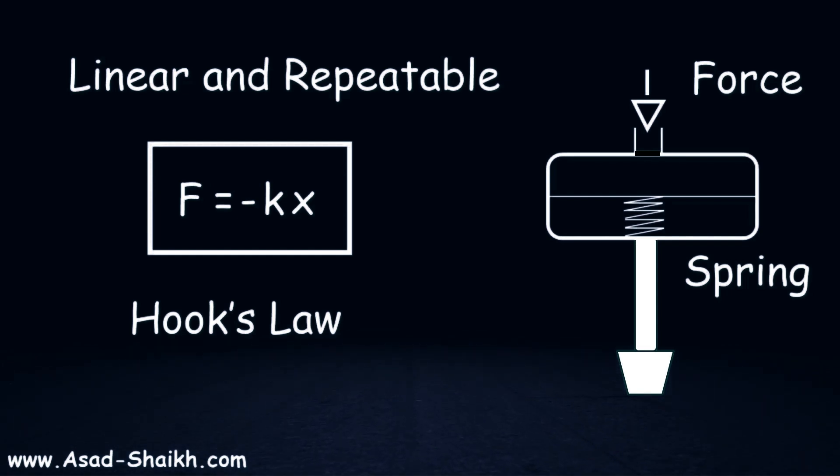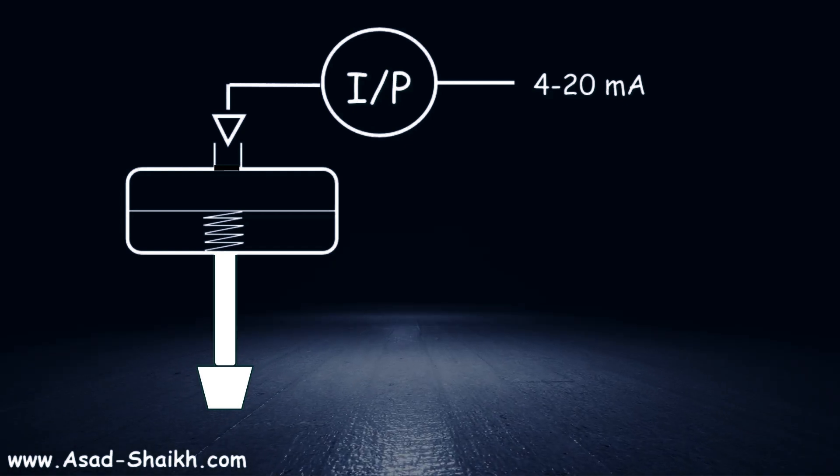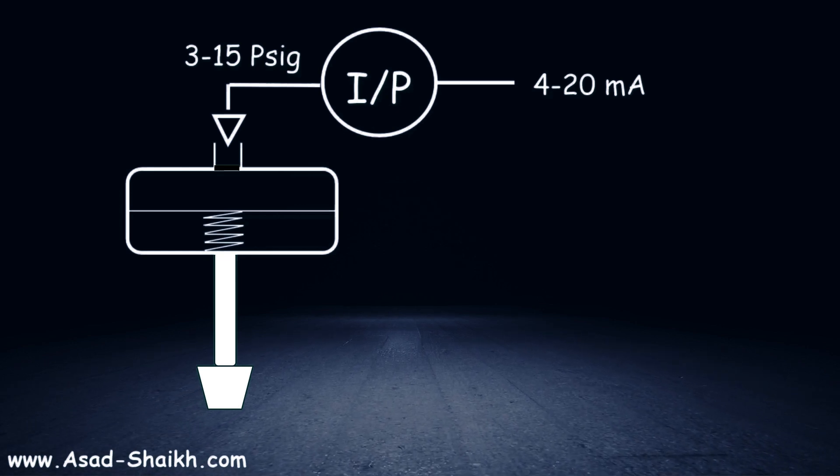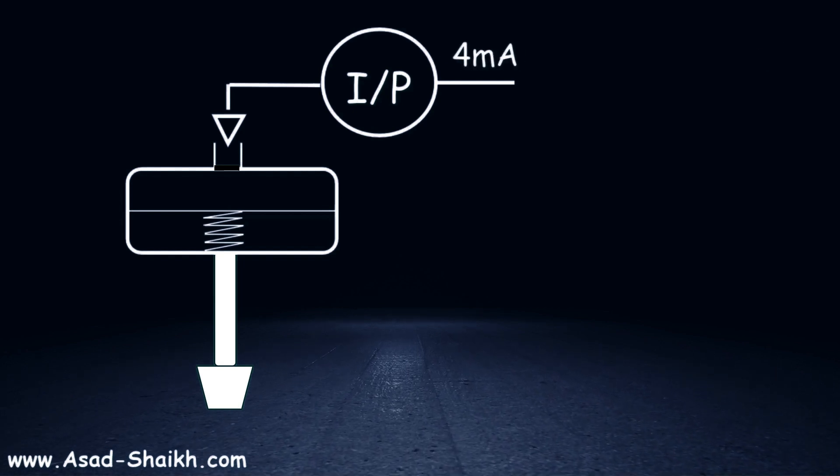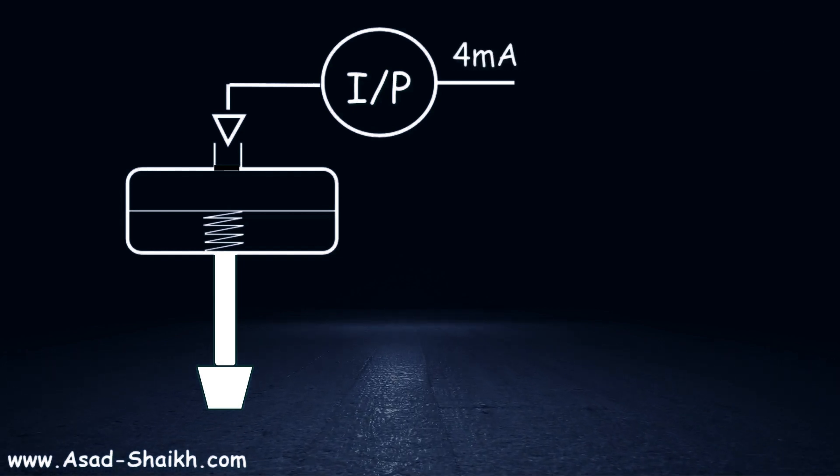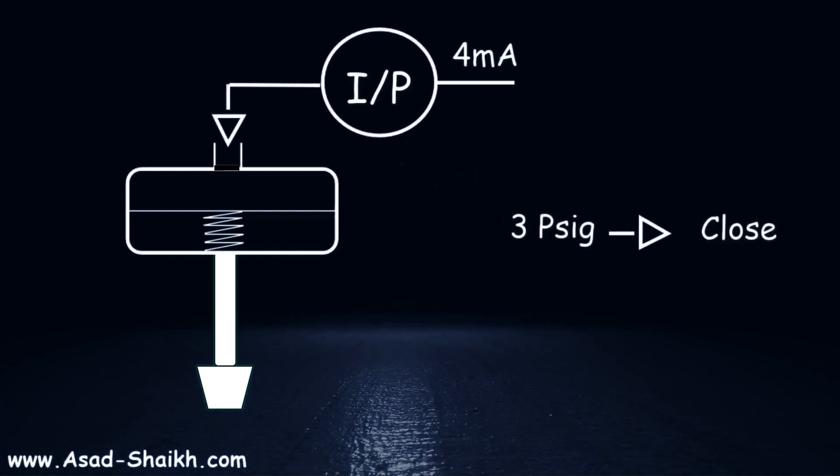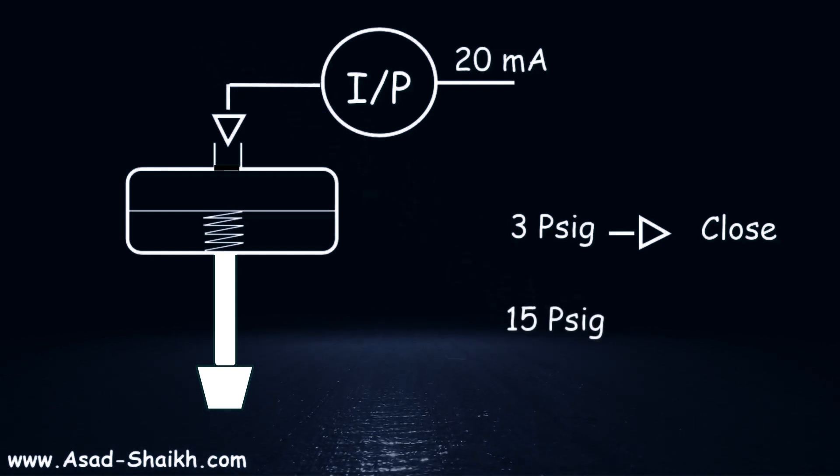When we hook it to an I/P converter, imagine the 4 to 20 milliampere signal that is coming from your control system can be calibrated to 3 to 15 psig, which will then be useful for you to control the valve. For example, if the control system signal is 4 milliampere, the I/P converter will convert it into 3 psig, which is the valve closed position. Then you get 20 milliampere from the control system, and the I/P converter would convert to 15 psig, which will be equal to the valve's open position.